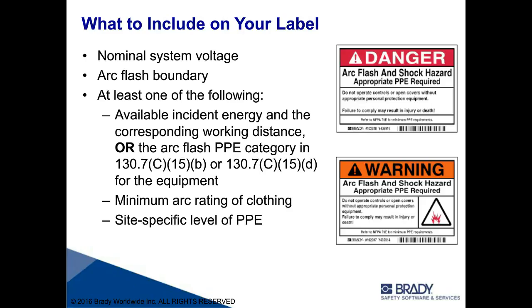Could be anywhere. I've seen them up in the hundreds of calories per centimeter squared at main switchboards. And that is always calculated right at that working distance, which is going to be 18 inches. 18 inches is the working distance that code defines. Key to note there, it says or the arc flash PPE category. If you look at pretty much every label out there prior to 2015, you would see the incident energy and a working distance, and you would also see an HRC category, that 0, 1, 2, 3, or 4.